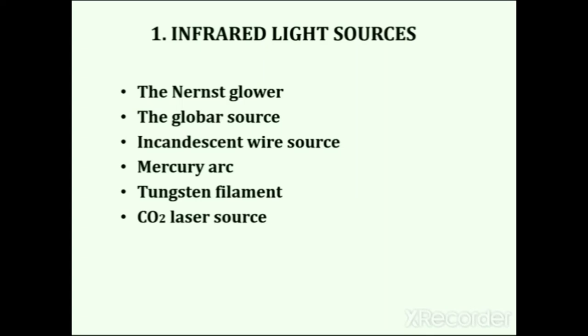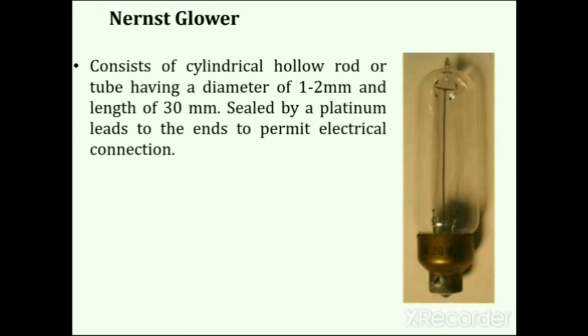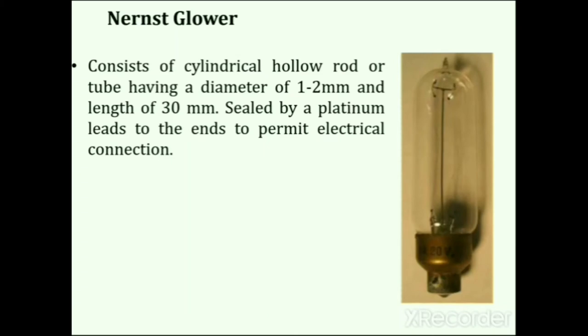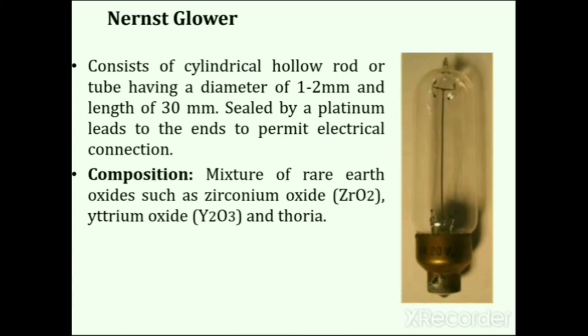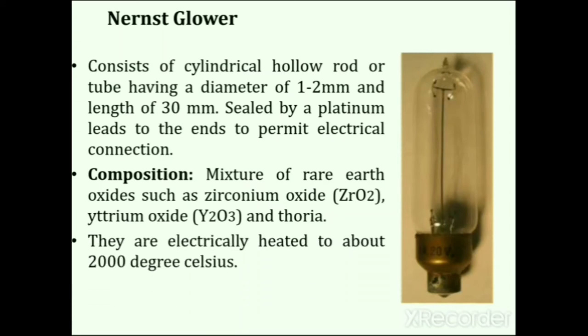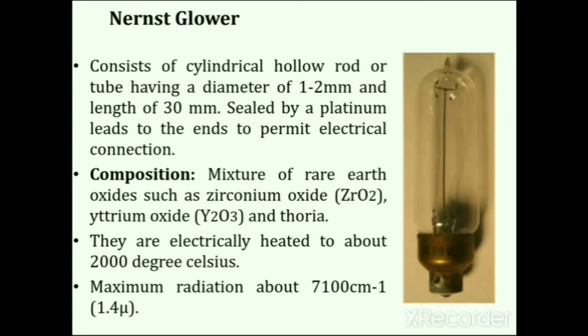Infrared sources consist of an inert solid electrically heated to a temperature between 1500 to 2200 K, which then emits infrared radiation. The Nernst glower consists of a cylindrical hollow rod or tube, 1 to 2 mm in diameter and 30 mm in length, sealed by platinum leads to permit electrical connection. It is composed of a mixture of rare earth oxides such as zirconium oxide, yttrium oxide and thorium oxide. When heated to about 2000°C, it generates IR radiation, providing maximum radiation at about 7100 cm⁻¹. Its lifetime depends on operating temperature and care in handling.